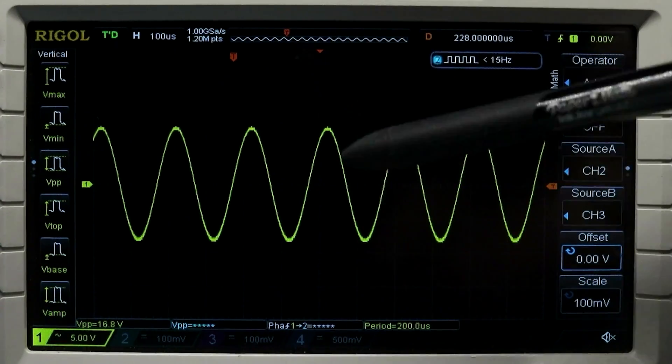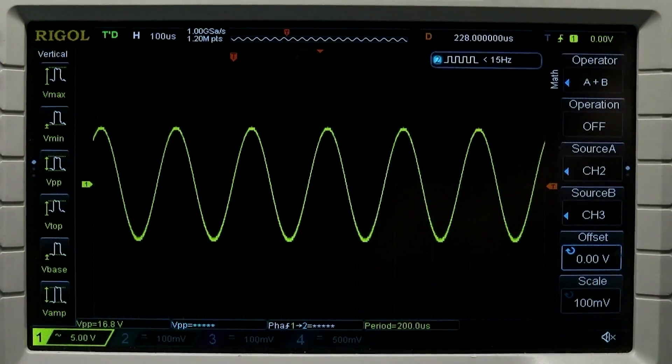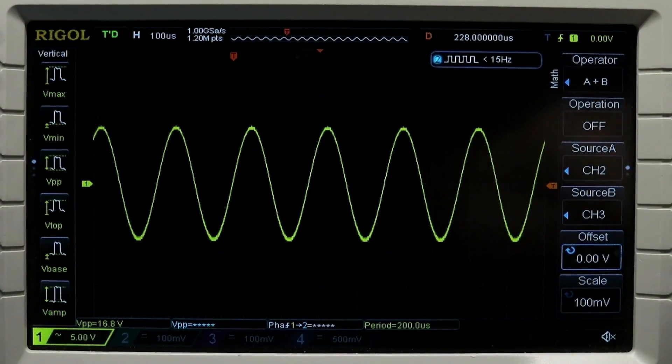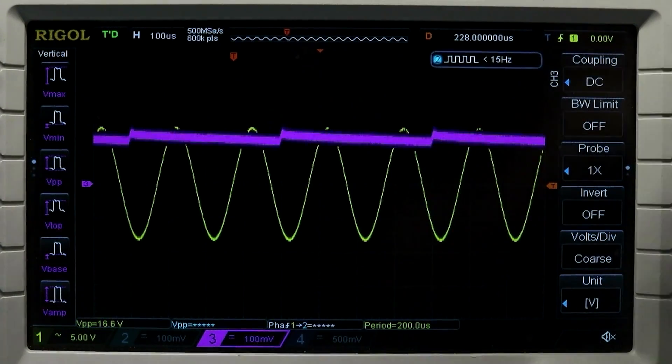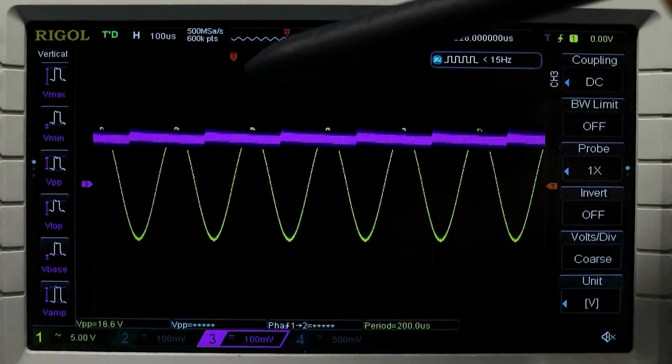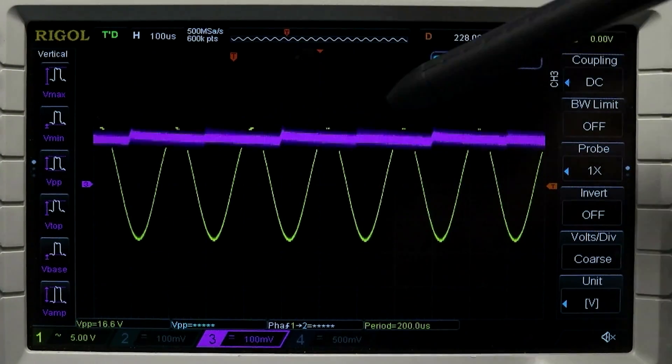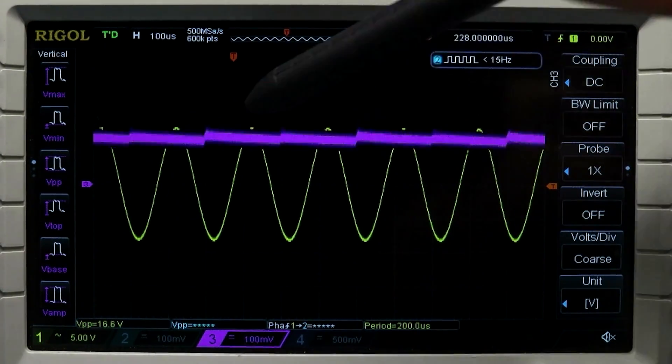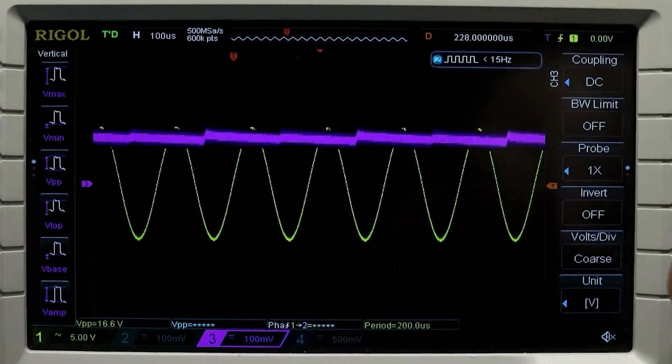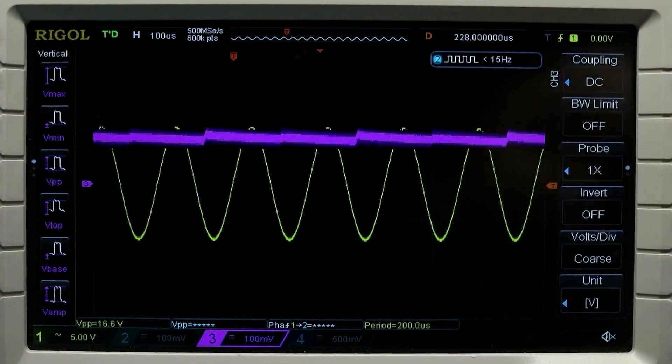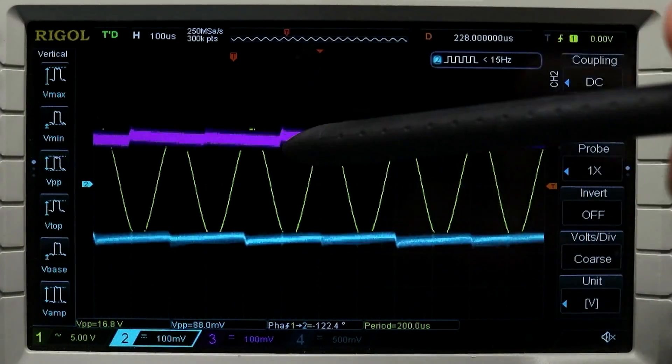So here is the excitation voltage at 5 kilohertz, the signal we're sending to the center coil of the LVDT. Now I've got that slug in the center of those coils so let's turn on the high side and you can see the output voltage. This is the output of the peak detector so it's a little choppy but we kind of expect that. We could do further filtering on this if we wanted to. That's the high side, let's look at the low side.